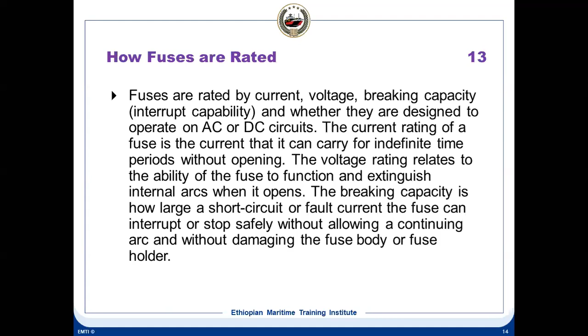So these things are very clear. Current rating is the current it can carry for an indefinite time period without opening, and voltage rating is related to the ability of the fuse to extinguish the internal arc when it opens. That's important. Breaking capacity is how large a short circuit or fault current the fuse can interrupt or stop safely without allowing a continuing arc and without damaging the fuse body or fuse holder. So fuse ratings are current, voltage, and breaking capacities, or we can say interrupt capabilities.